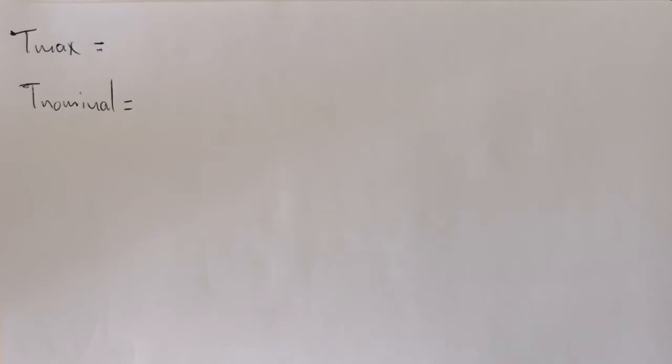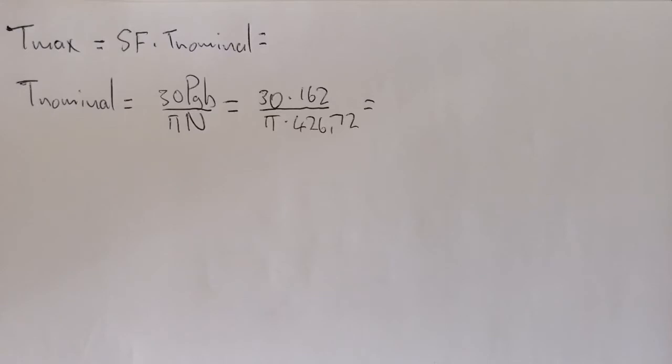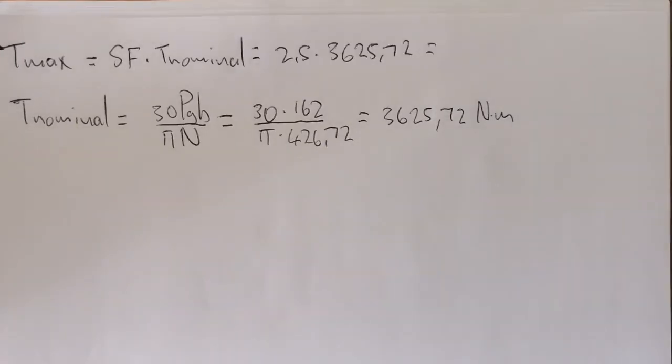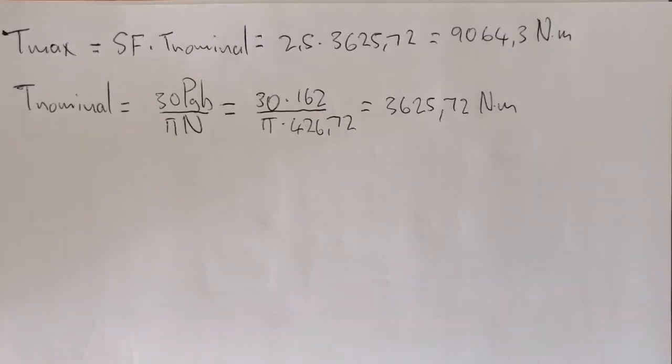Now let's look at the maximum torque and the nominal torque. Maximum torque is service factor times the torque nominal. Nominal torque is 30 times the power of the gearbox over pi times the speed of the gearbox. This equals 3625.72 newton meters with a maximum torque equal to 9064.3 newton meters. The maximum torque is what the coupling can handle if you select it right. The nominal torque is what the coupling actually operates on.